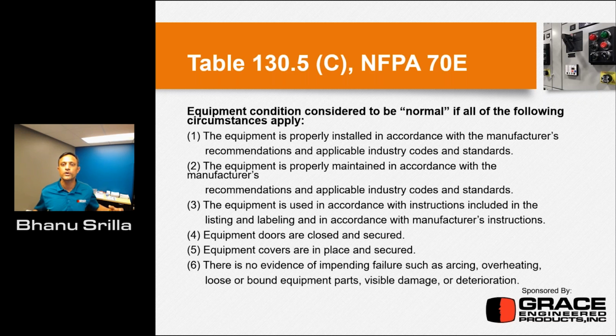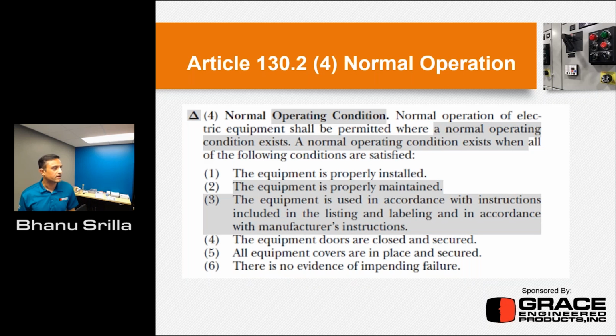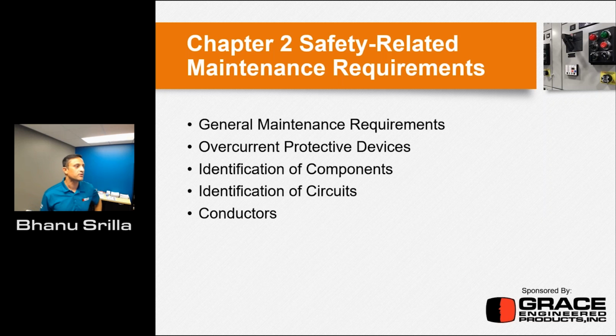So this is basically when you go and look around this equipment physically, just a walk-in inspection, you need to make sure that there are no visible or imminent failures around this equipment, okay? So this is again from Article 130.2, which covers normal operation. The same thing, basically, you need to follow the six steps before the equipment is construed as in normal operation, okay? So Chapter 2 talks about the safety-related maintenance requirements when it comes to electrical equipment. This is part of NFPA 70E, which talks about the general maintenance requirements, the requirements for the overcurrent protective devices or OCPDs, identification of the components, identification of circuits and conductors.